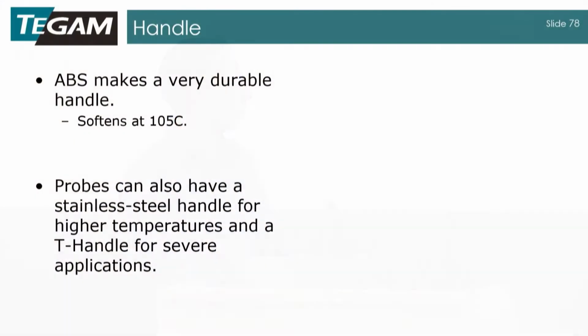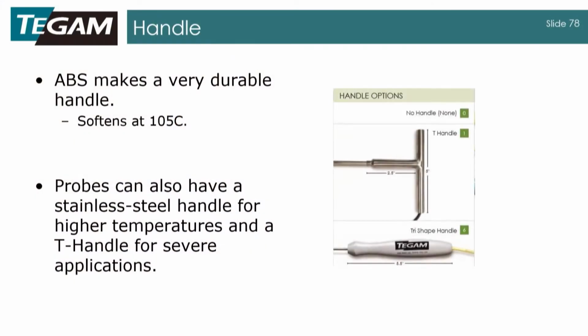If you're going to be in something that's hotter than 105 degrees C for a longer period of time, you might want to look into something like a stainless steel handle for higher temperatures. A lot of times the stainless steel handles will look like a T, and there might be some type of a ceramic transition right there just to keep the T handle from getting hot as quickly as the thing that you're measuring. So basically the handoff there is that your stainless steel handle isn't going to melt, but it still could get fairly hot. So you need to keep that in consideration for whoever's going to be holding the probe. They probably appreciate you for that.